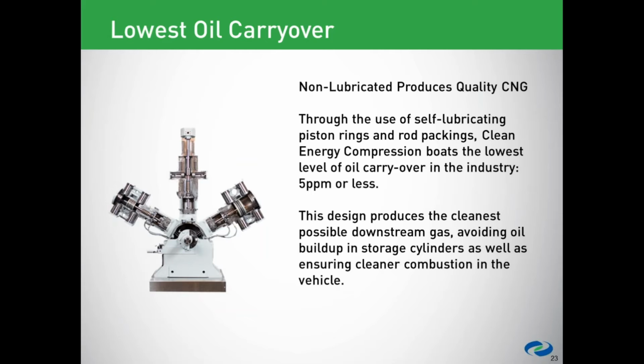So our focus is don't introduce the oil at the beginning. Certainly don't inject it into a cylinder and then try to remove vaporized oil from a hot gas stream, which many of the engineers out there will know is less than a science. And then, of course, you have to deal with the disposal of those oil-soaked filters and, of course, the storage of the oil on site.